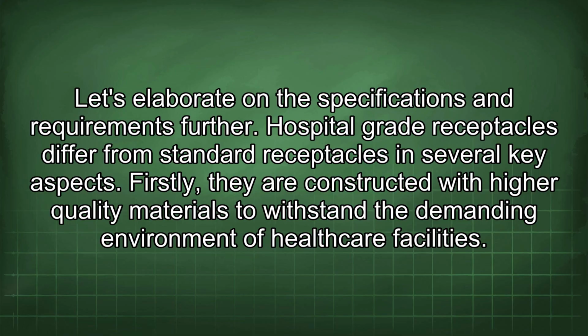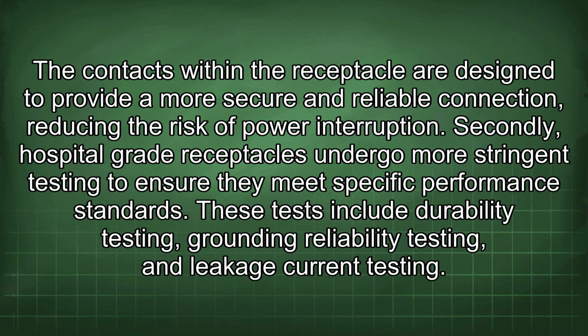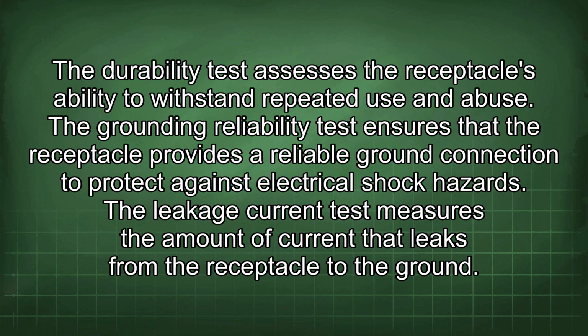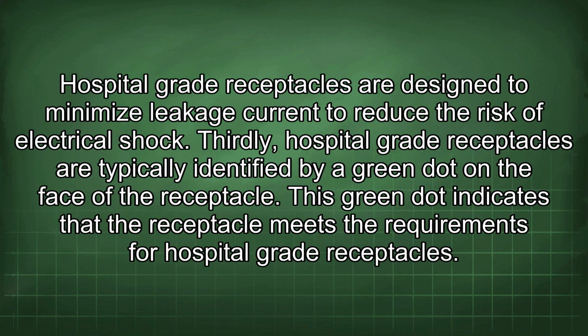Hospital-grade receptacles differ from standard receptacles in several key aspects. Firstly, they are constructed with higher quality materials to withstand the demanding environment of healthcare facilities. The contacts within the receptacle are designed to provide a more secure and reliable connection, reducing the risk of power interruption. Secondly, hospital-grade receptacles undergo more stringent testing to ensure they meet specific performance standards. These tests include durability testing, grounding reliability testing, and leakage current testing. The durability test assesses the receptacle's ability to withstand repeated use and abuse. The grounding reliability test ensures that the receptacle provides a reliable ground connection to protect against electrical shock hazards. The leakage current test measures the amount of current that leaks from the receptacle to the ground. Hospital-grade receptacles are designed to minimize leakage current to reduce the risk of electrical shock.